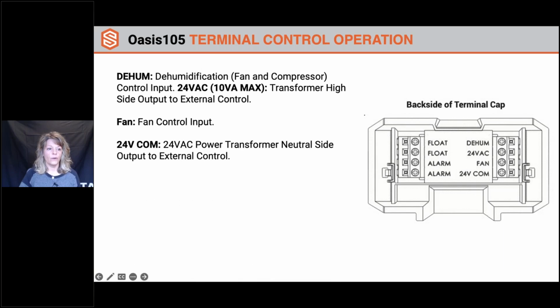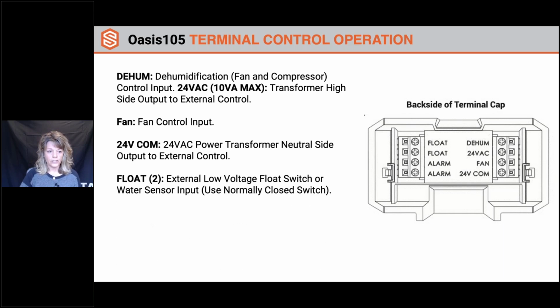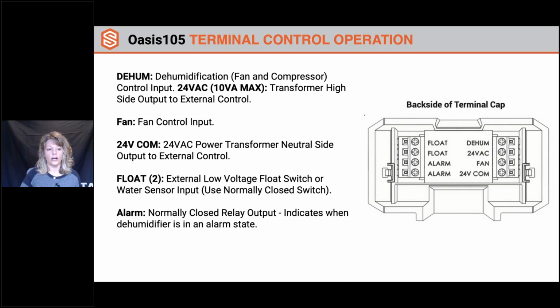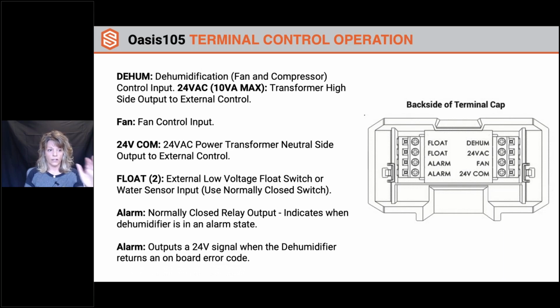Fan control input, we've got 24-volt common, the power transformer, float switch there. So when we talk about that secondary drain pan, you can wire and screw in a float switch here. And then there are alarms that can be used with this unit as well. Let's say you have a crawl space and you want to use an external controller to indicate if there's water in the space, then you can wire it here as well. So a lot of things, if you're on the HVAC side, very common to what you're used to in this terminal block.